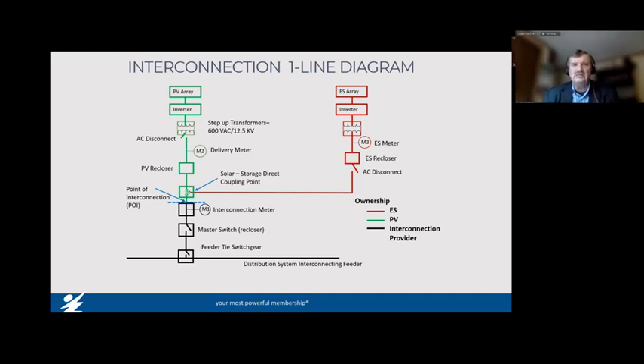Now, over on the right, ES array, energy storage array. That is the batteries. Each one of those battery containers is 1 megawatt capacity, 2 hours or 2 megawatt hours. On the Ramsey site, which we visited, there are 6 containers, therefore 6 megawatts of capacity, 12 megawatt hours of total energy. And that goes also through a series of inverters that change the output from 1500 volts DC to 600 volts AC, up through a series of transformers, again to the distribution grid voltage, again through a recloser, again a pad mounted circuit breaker, and that can be tripped to isolate the batteries from the rest of the system, through a disconnect switch, and then cables over again to this giant wire nut, the 3-way junction box.